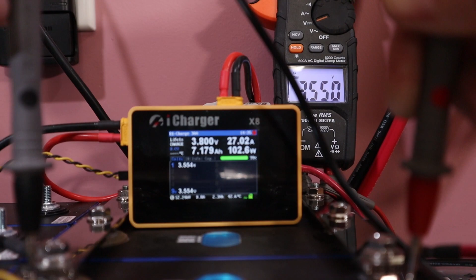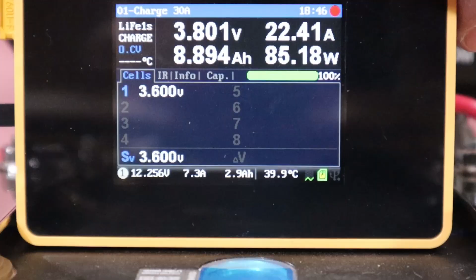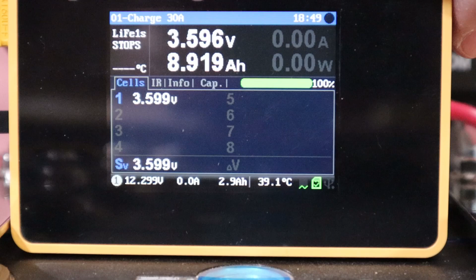The amperage is ramping down. It's showing 100% state of charge, but obviously it's not because it's still taking in power. 3.584, getting really close, really quickly. 3.59, still running at 3.8 volts. If it hits 3.60 and it's still going, I'm stopping it. I don't think it's going to stop - it's still putting 22 amps in.